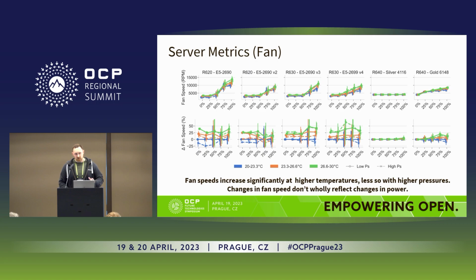So what we see is, across the board, when you raise that upper limit of temperature to, say, 28 degrees, you're seeing a 2 to 6% decrease in energy efficiency. But only 2 to 3% of that is caused by fan increased rotation. The other 3% at a base level is leakage current generally. And John will probably back me up on this one tomorrow, perhaps. But fundamentally, running IT hotter isn't just about it being harder to cool. There is a direct onboard impact from running systems hotter, and that is through leakage current. That's the interplay between the CPU and the system board.